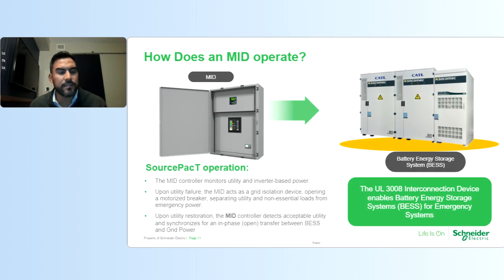So how does this microgrid interconnection device operate? Well, SourcePacT, our product, has a controller that monitors utility and inverter-based power. So the controller is monitoring utility power on top of the breaker, source one, and at the bottom it is monitoring inverter-based power. Now, upon a utility failure, this microgrid interconnection device acts as a grid isolation device. So it opens that electrically operated breaker, separating the utility and non-essential loads from emergency power.